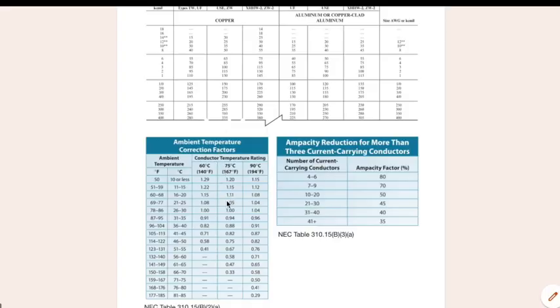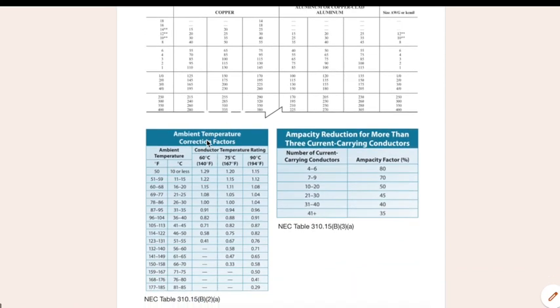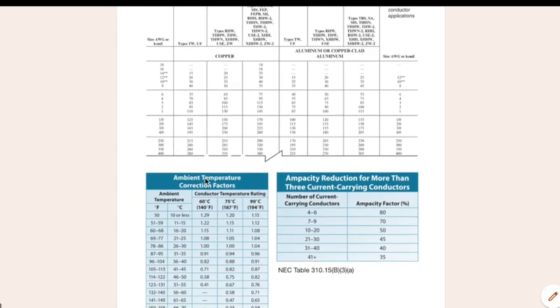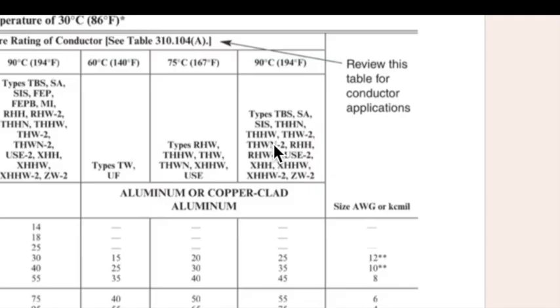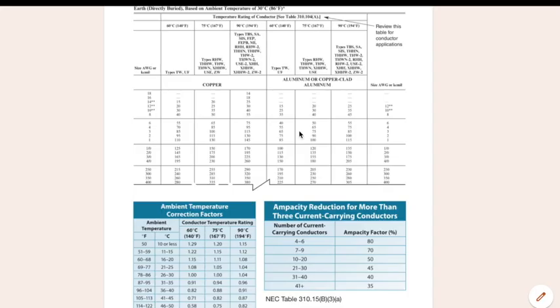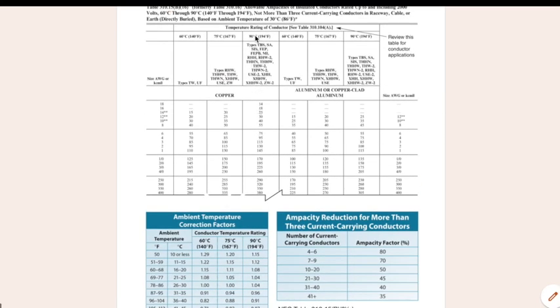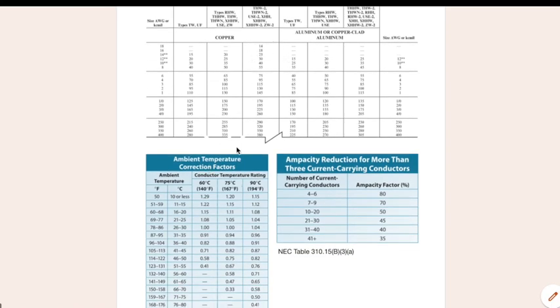So if I'm talking about type UF, when I come down here to find the correction factor I must apply, I'm going to do it in the 60-degree chart because that's where I find UF. Equally, if I'm looking for THHN aluminum, which I believe is over here in the 90, THHN, yep, there it is. I'm going to use the 90-degree chart over here just as I would if I was using THHN copper because that's still in the 90-degree. I hope that makes sense to you guys how to read this, and I hope that this example helps you.